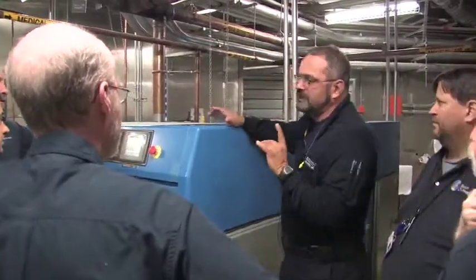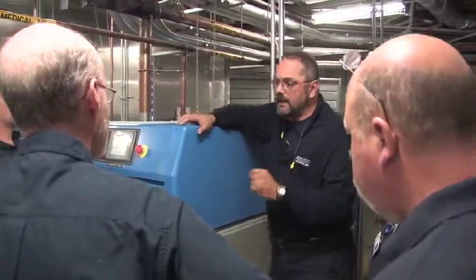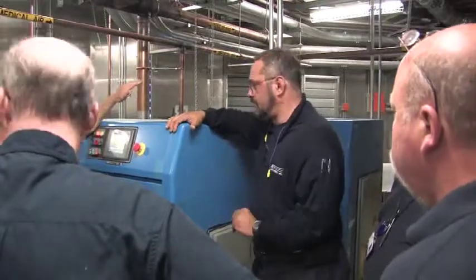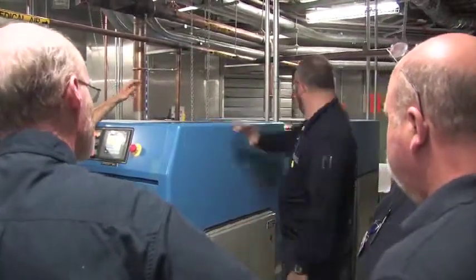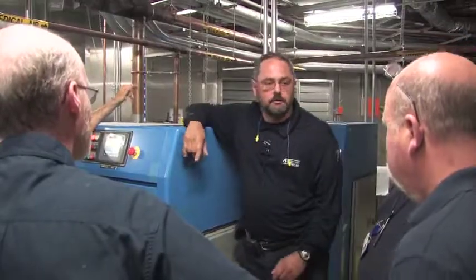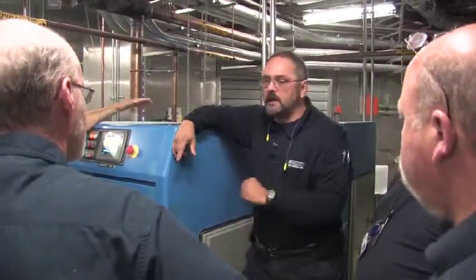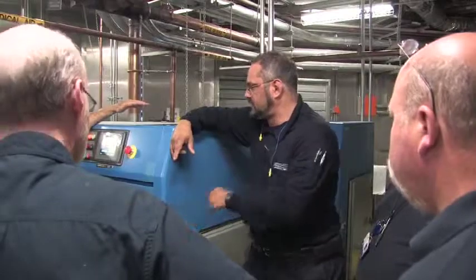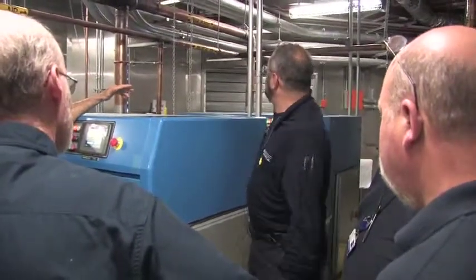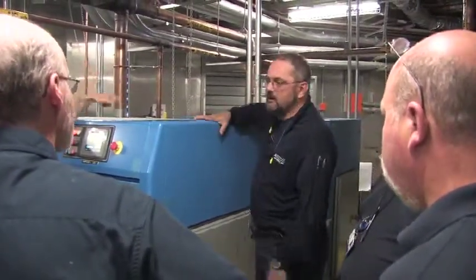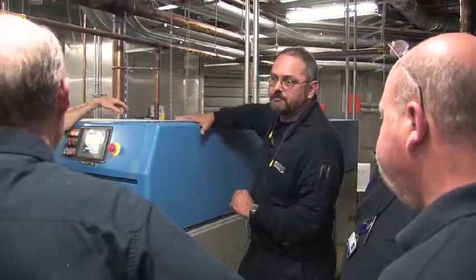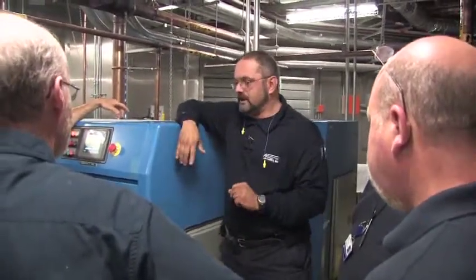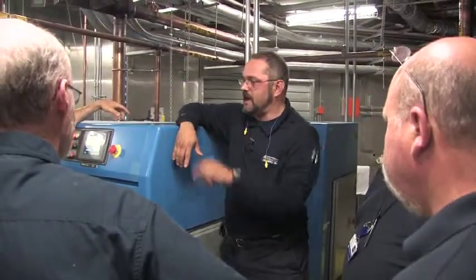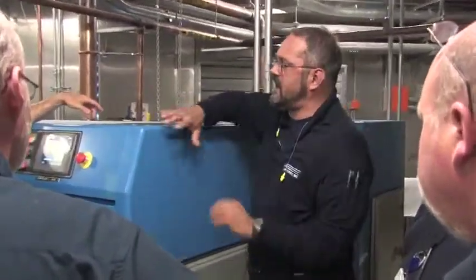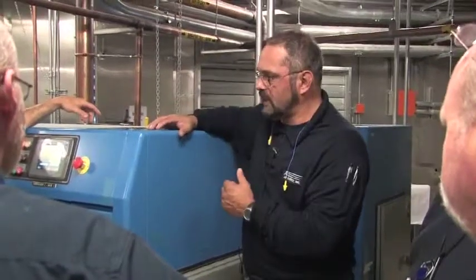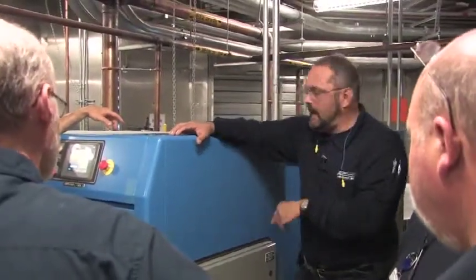Because now bear in mind, the other thing that's going on with this particular iteration is there's a network switch in here. There's a network switch in there. So the communication between these is actually an Ethernet connection between those switches. That one is connected from there into the switch in here. The switch from here goes over to there. So they're all talking to each other. But by the same token, that's the master. I kill that, these two lose signal from the master, they revert to local.